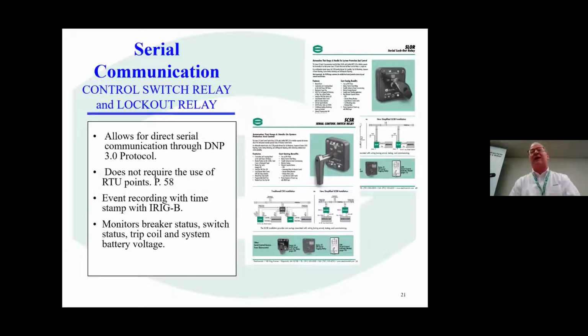So with this, you can actually map out, in many cases, control centers at substations and control rooms for utilities will have a video graphic of all the devices they have in their system and all of the lockout relays and all of the control switches and all of the breakers in a nice visual graphic format that they can monitor and do an overview and understand what's going on out in the field on every substation in their network.